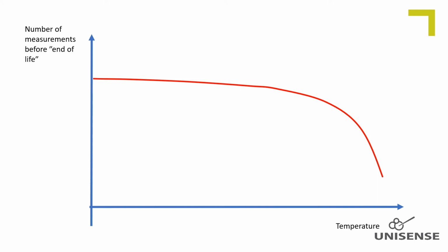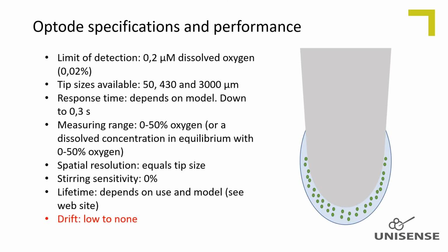Shelf lifetime, if the optode is stored in the dark, is very long, more than 3 years. The optodes are long-term stable and do not require frequent calibration. As the phase shift to a minor extent changes with bleaching, we do, however, recommend to recalibrate the optode for all important measurements. During high-frequency measurements, recalibration should be done more often compared to low-frequency measurements.